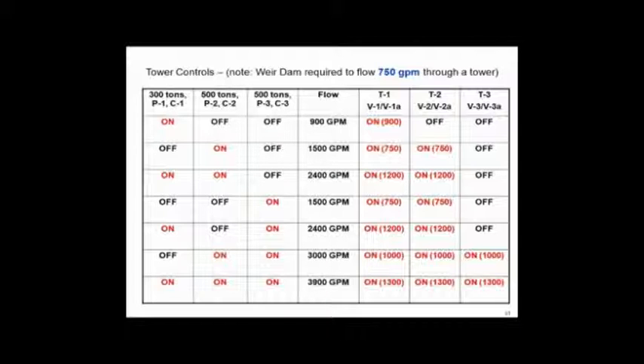So here we go. I've got three towers. I've got weir dams in my towers. The minimum allowable flow rate is 750 GPM. They're 500 ton towers, 10 degree range, 3 GPM per ton. So 300 ton towers have a flow rate of 900. 500 ton towers have a flow rate of 1500. Let's look at the little staging sequence here to see if we can understand this.